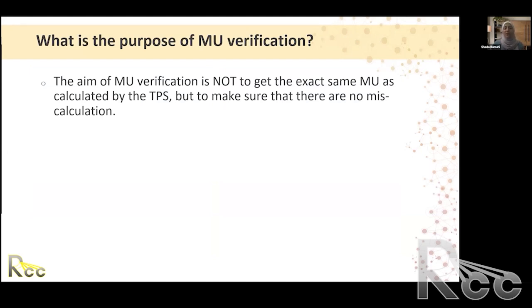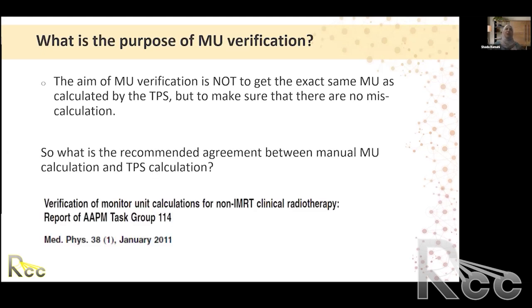What we're trying to verify is that there are no computer bugs, there are no mistakes, there are no large discrepancies that will end up with a patient getting overdosed, or other issues with the patient. So we're not looking for an exact number. We're looking to make sure, does it look good? And so in this case, now we're looking at what the allowed difference is. Is it 2%? Is it 3%? Is it 5%?